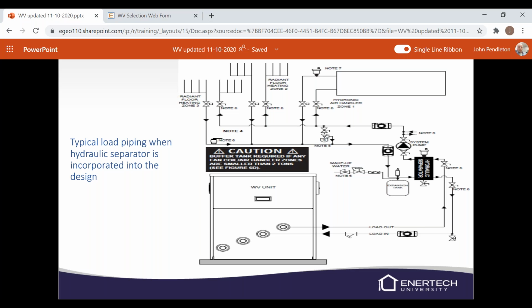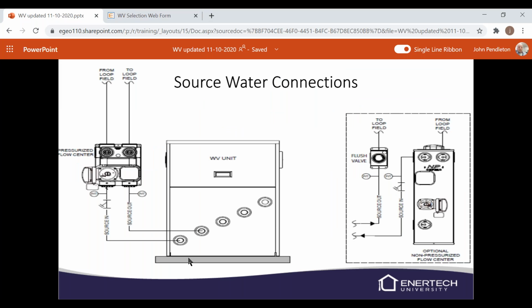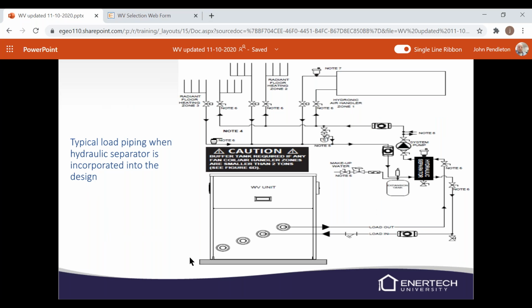So this is the typical load piping when there is a hydraulic separator incorporated into the design. Basically, the hydraulic separator is like a small buffer tank. You're decoupling the flow requirements for the unit from what your flow requirements are from your zoning. So you have the hydraulic separator, you've got an external system pump, you've got some flush blocks in the external piping, so you can flush your zones.